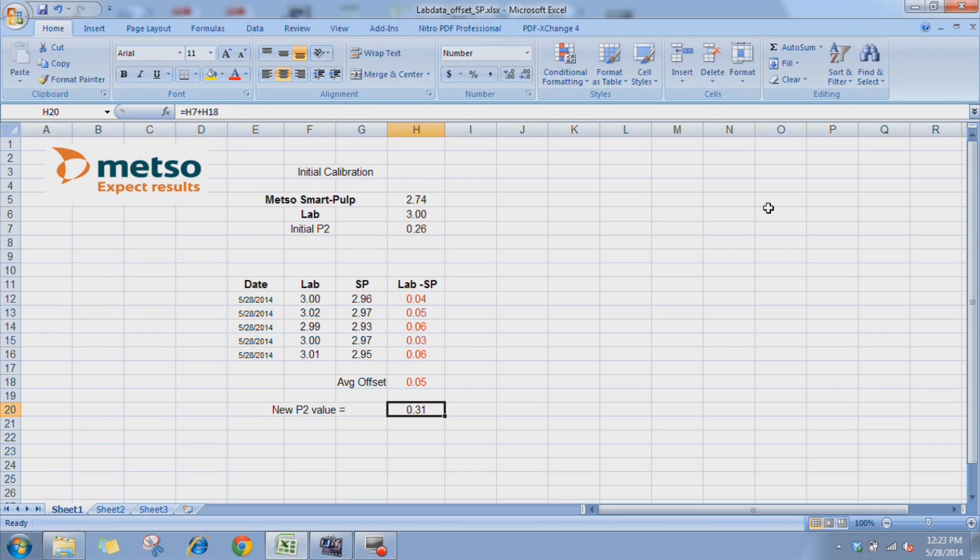We are basically checking our initial calibration and allowing statistics to work for us with the follow-up samples. So here, as we see, the SmartPulp was initially reading 2.74. Our lab came back and said the actual consistency was 3.00. The difference was 0.26. We put that into our offset. It brought the SmartPulp reading up. Now, as we took follow-up samples, we see the average offset of the five follow-up samples was 0.05. So we simply add the 0.05 to our initial P2 value, and the new P2 value would be 0.31. They're basically additive.